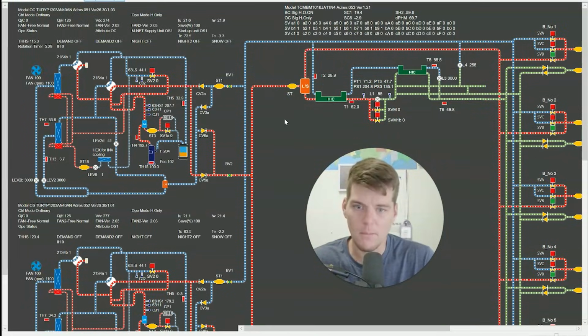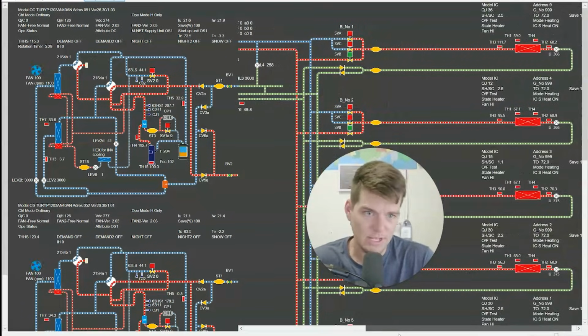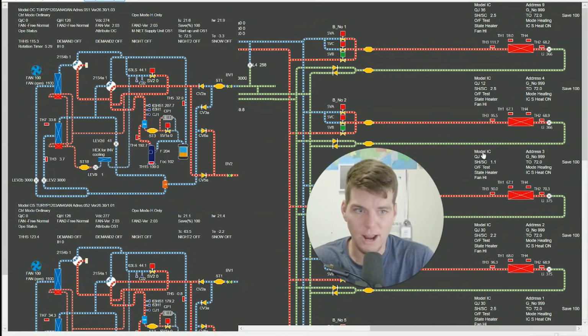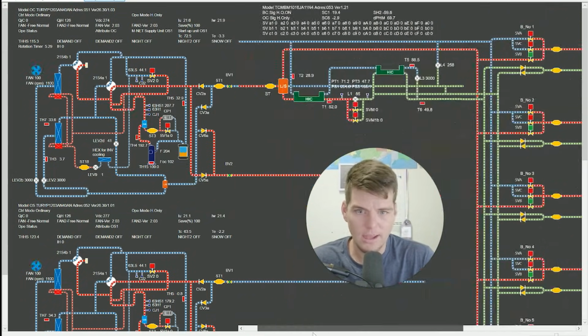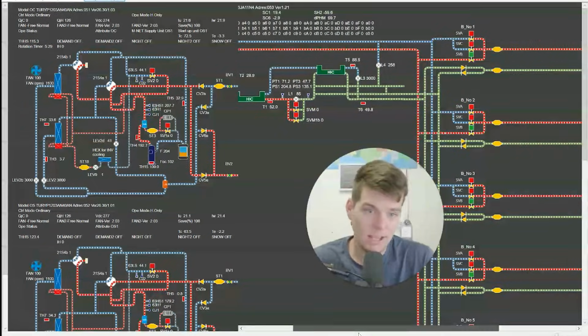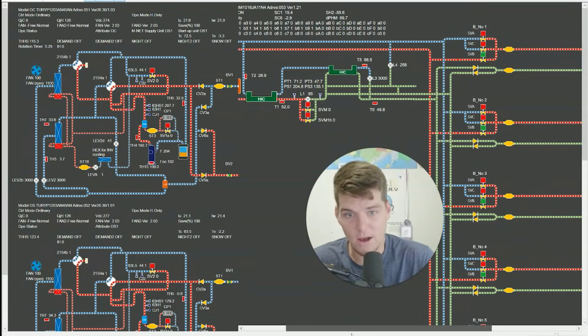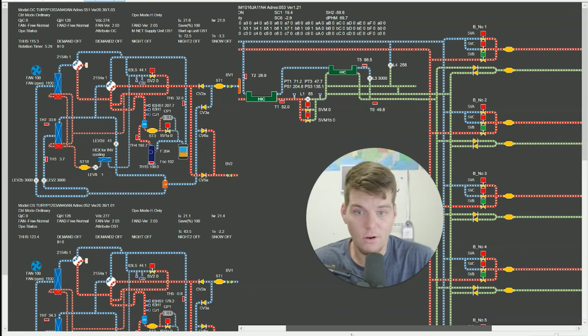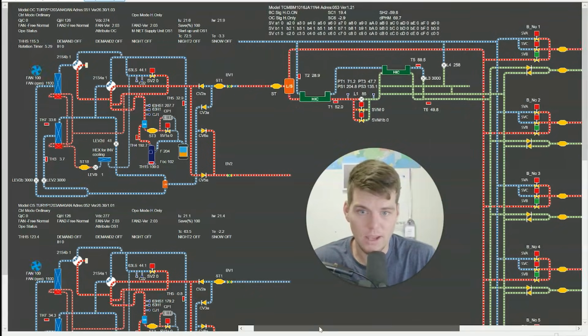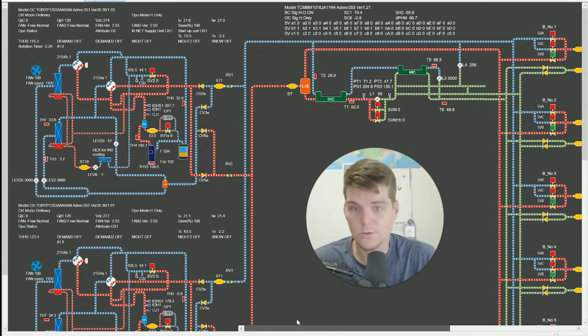Now, remember that I don't want to measure it after the box because we've got some subcooling magic going on here in these HIC plate-to-plate heat exchangers in the box itself. So more so, maybe I want to go to my indoor units and see what kind of refrigerant output I have through these units, right? That's turning this into a liquid, right? So we have hot gas that's coming in, we have liquid that's coming out, and then that is being fed all the way across to my outdoor system, right? Let's stay focused here on what we've got going on.